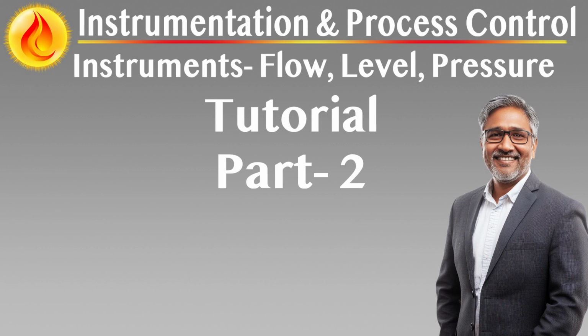Instrument design must withstand the full range of process and environmental extremes. Pressure and temperature limits for all pressure-containing parts in plant instruments must fully match or exceed the host system. For inline instruments, e.g. control valves, inline flow meters, this means full compliance with the assigned piping class, including transients and abnormal conditions. For online instruments, e.g. transmitters connected via impulse lines, the pressure-containing components must meet the same standards unless isolated by certified block valves. In such cases, limits must match the design pressure of the equipment, not necessarily the full class rating.